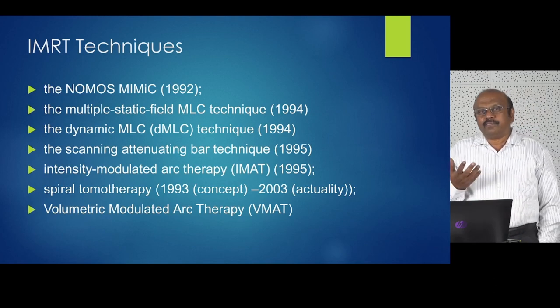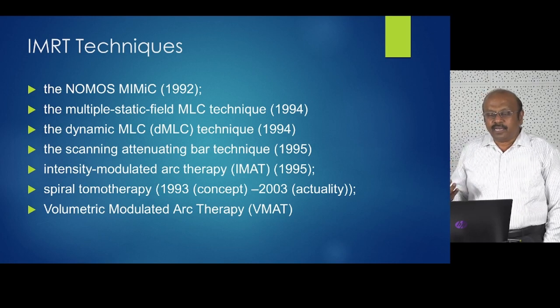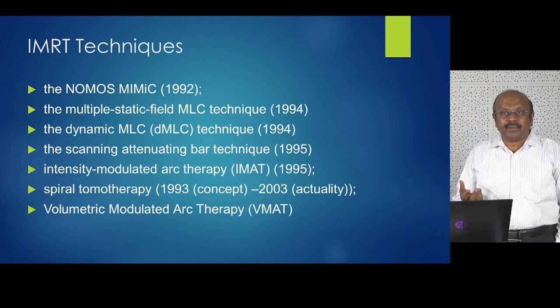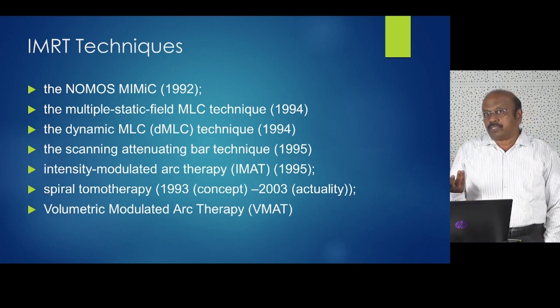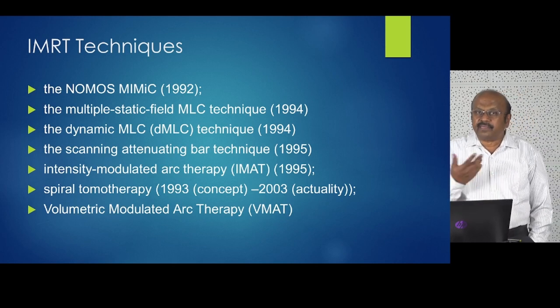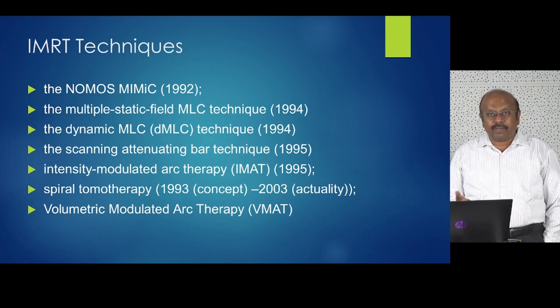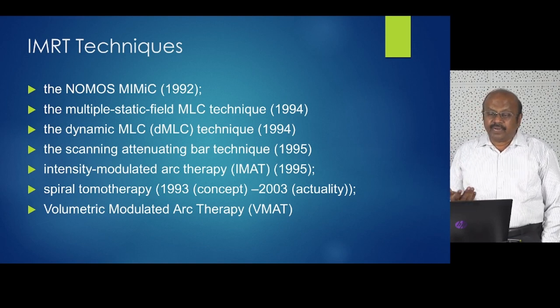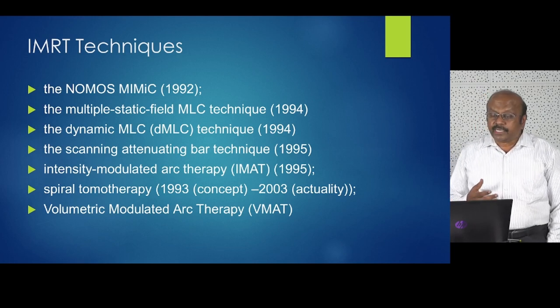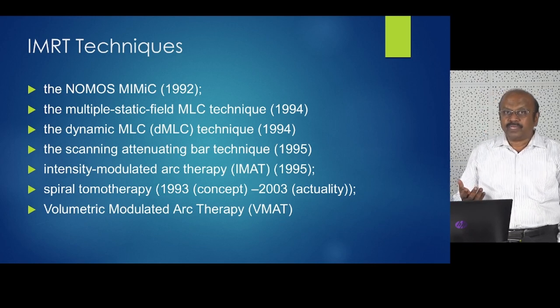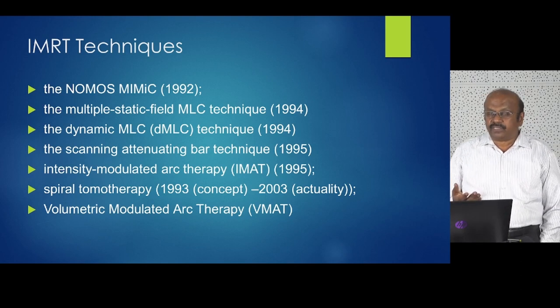The IMRT techniques evolved from 1992 by different methods. Initially they used what they call NOMOS MIMIC in 1992, then multiple static field MLC techniques starting in 1994. Dynamic MLC came and changed the method of delivery, and most Varian machines are dynamic. A scanning attenuation bar technique came in 1995, and intensity modulated arc therapy also in 1995. Spiral tomotherapy concept came in 1993 but commercially came up around 2003.